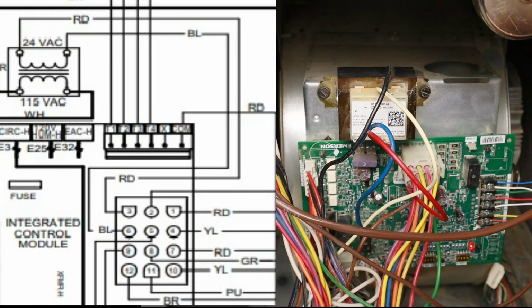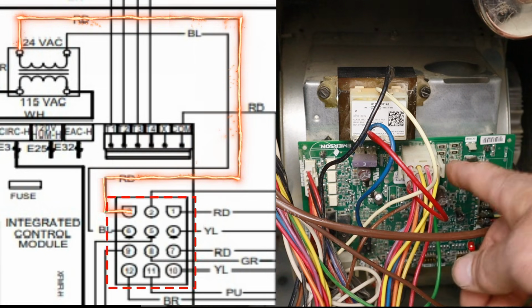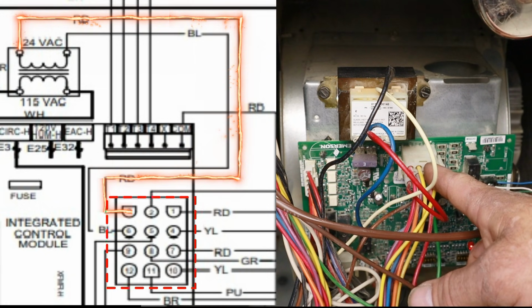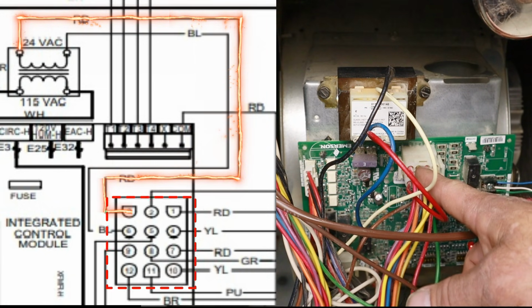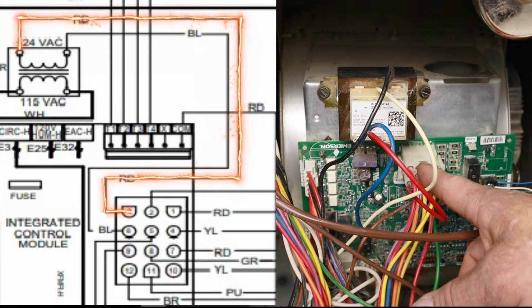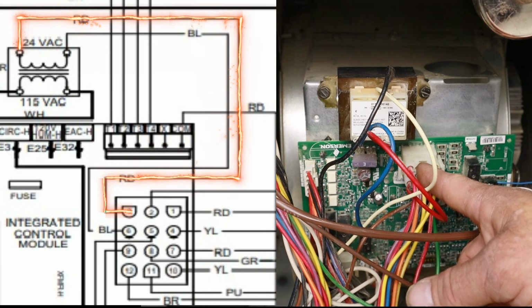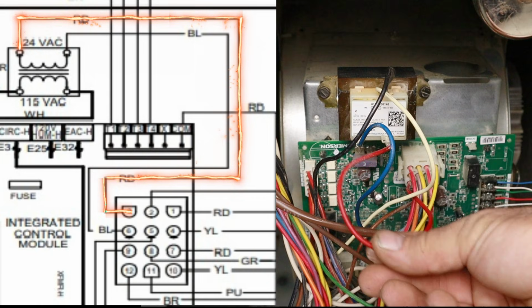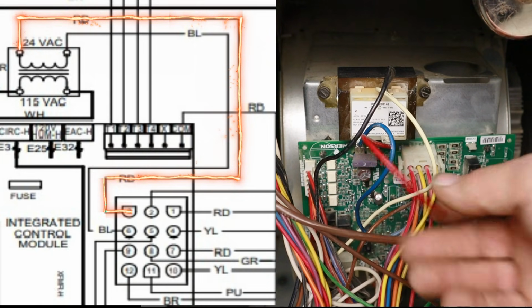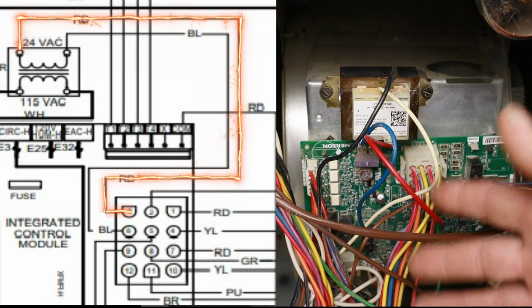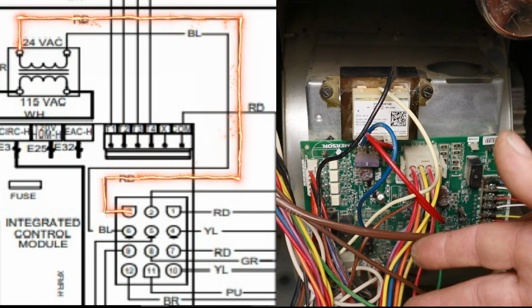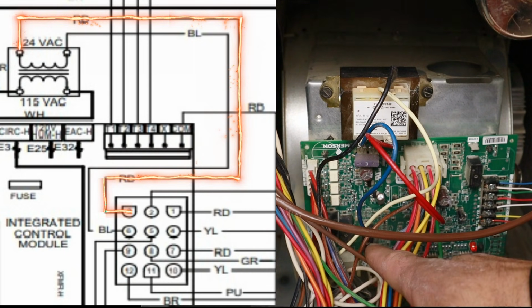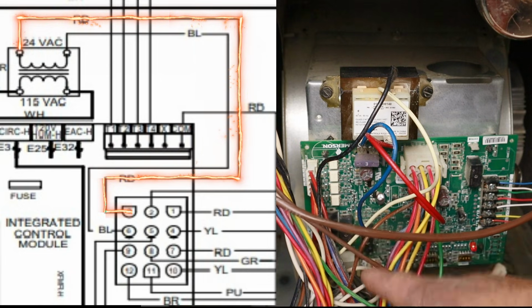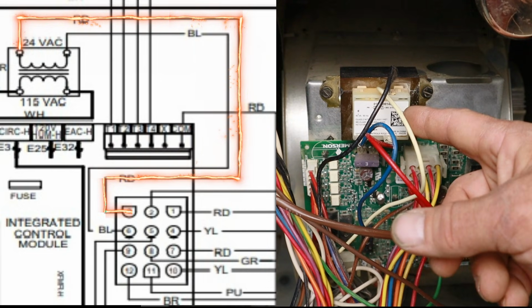So going back to our full schematic again, we see that red wire coming off our transformer, and it goes down into our Molex plug here. Now some units it might go into a Molex plug, on other units that wire will go directly into a terminal on a control board, but either way, this is our red wire here going back to the control board, and this is a pretty standard setup. You're going to see power coming into the control board, 120 volts. That power is going to go into the transformer at 120.